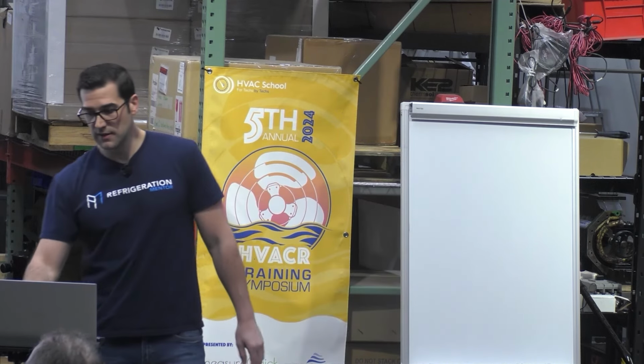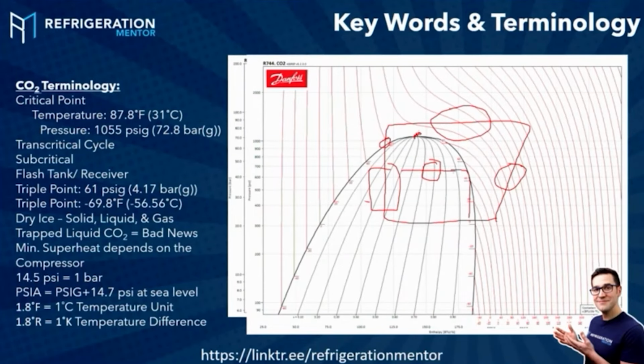So we have liquid going out as we leave. We go to this point. Remember we talked about this bubble point? This bubble point is where we have full liquid. When we leave a receiver, we'll say we have this much liquid inside here. We got liquid, and that goes down through, so that's how it probably should be drawn, that first red line probably shouldn't be there for the transfer. So this is my evaporator.